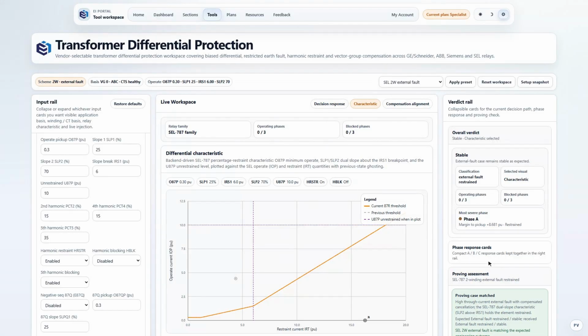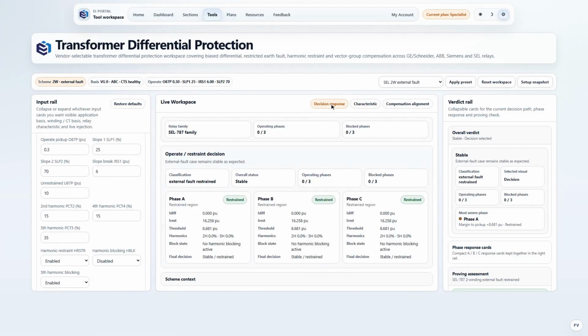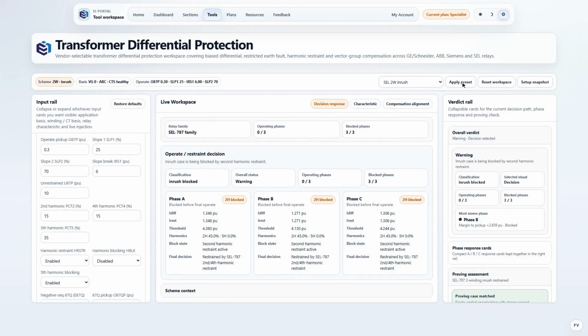Now for the false trips. Energize the transformer and magnetizing inrush pours differential current into the relay, 1.35 per unit here, with no fault anywhere. The tell is second harmonic, 45%, 3 times the 15% threshold. Watch what the 787 does. Harmonic restraint hoists the operating threshold to 4.38 and the element rides through, resulting in a warning, not a trip.